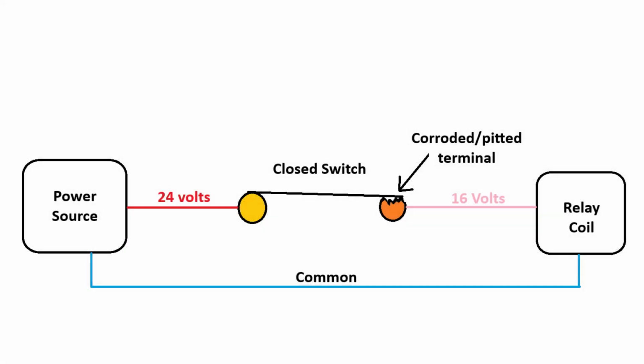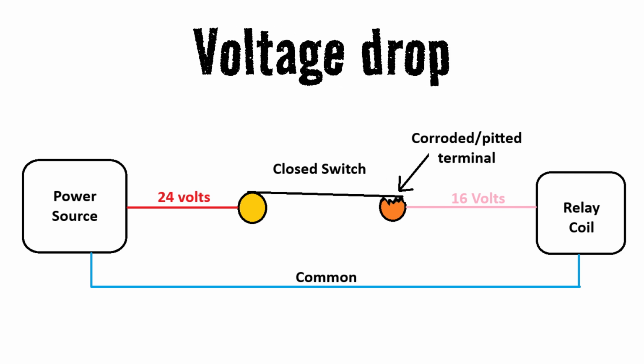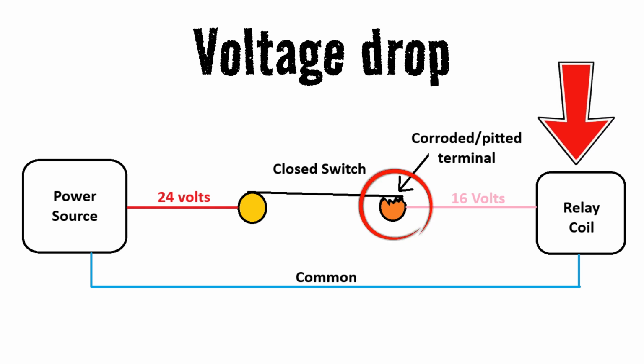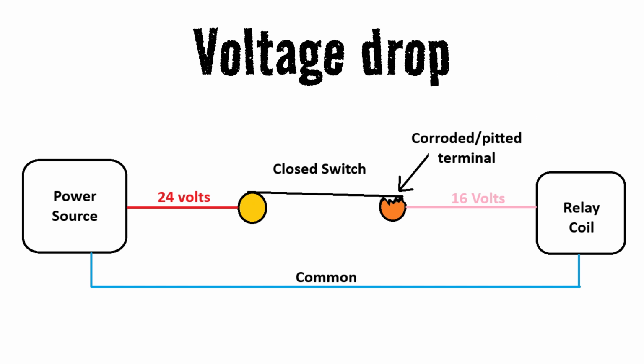Now, one last thing I want to talk about is voltage drop. This one definitely threw me for a loop and had me tracing circuits for hours the first time I ran into it. In a nutshell, voltage drop is an unintended form of resistance in the circuit somewhere prior to the component we actually want to power and activate. So for example, if we're trying to push voltage through a corroded terminal on a switch or a control board, that little form of resistance will have the voltage trying to push current through it. And these forms of resistance can turn that energy into heat.